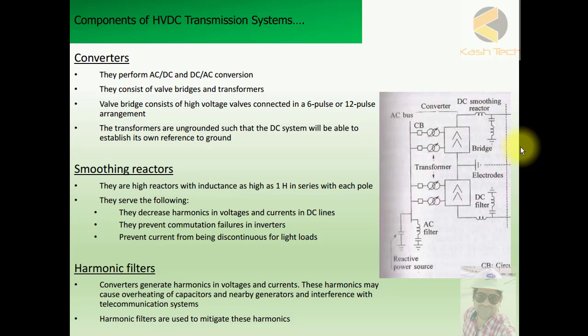This is a very important point: the transformers used in DC systems must be kept ungrounded because the DC system has to use its own ground. Smoothing reactors are large reactors with inductance as high as 1 Henry, connected in series with each pole. In the diagram here you can see the DC smoothing reactors, the DC filters connected after conversion from AC to DC, and the AC filter connected to the AC side of the network.